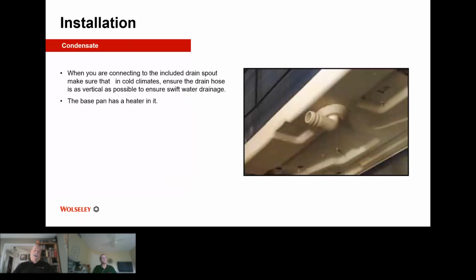As I was talking to you before, this is an example of your condensate port at the base pan of your outdoor heat pump. Most manufacturers have a heater in the base pan so that the condensate that is in there will never ice up. What you can see when you look at the bottom of the outdoor units is that the unit has been specially designed to flow condensate when it collects to the port. It's not flat in there. It's angled and it's made to flow to this. And so that way, the condensate, when it's rolling off, whether it's in the heating or cooling mode, it will get away from this unit and no ice will build up in the bottom at all.